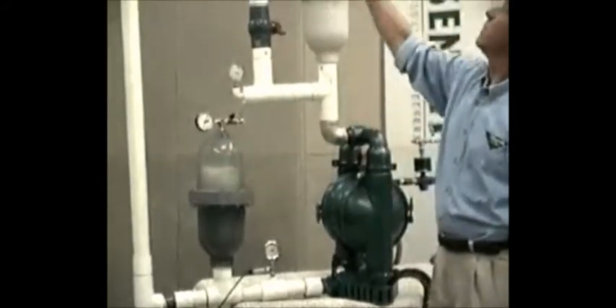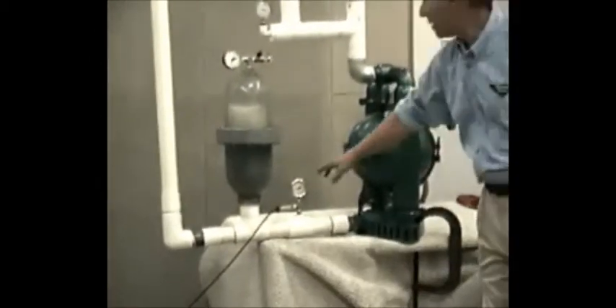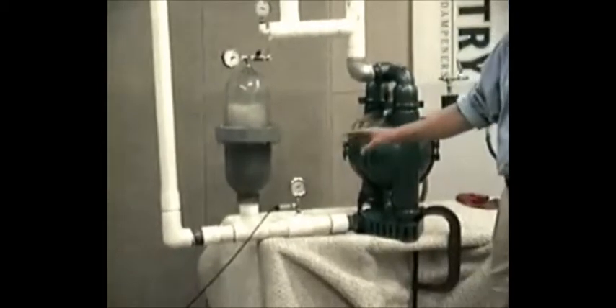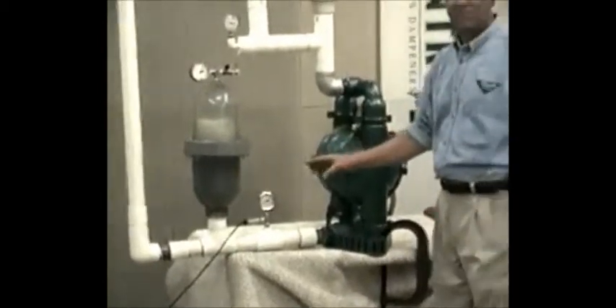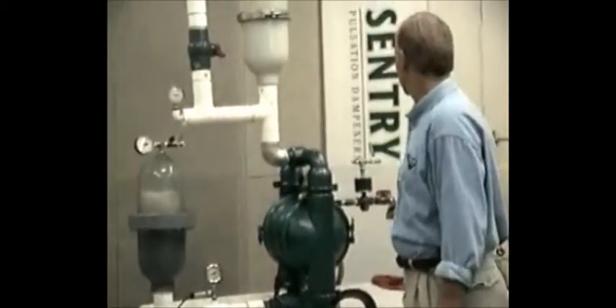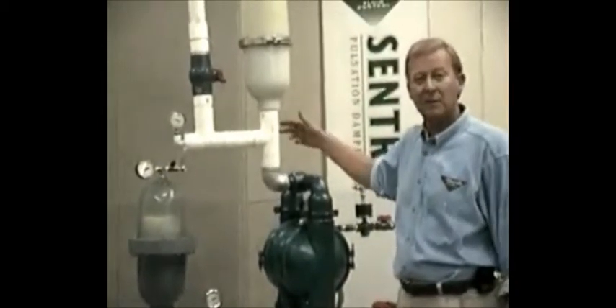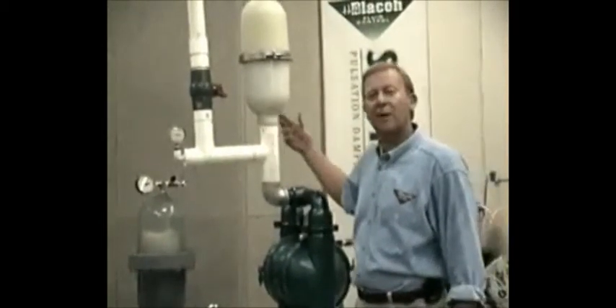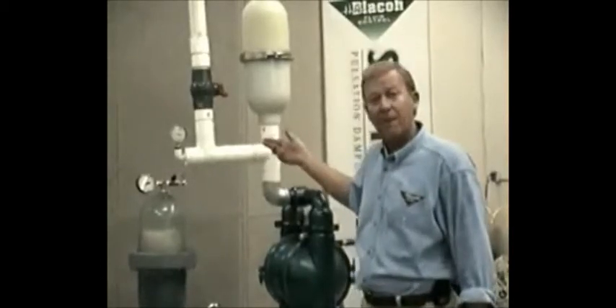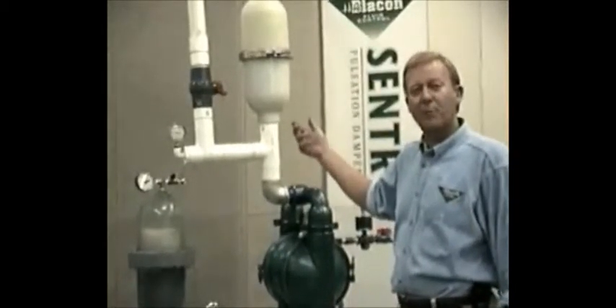Also observe that the inlet pipe is now vibration free and protected from damage to joints, threads, gaskets, gauges and other components on the inlet side of the pump. We have in effect turned a reciprocating positive displacement pump into a centrifugal pump from a flow and pressure point of view.